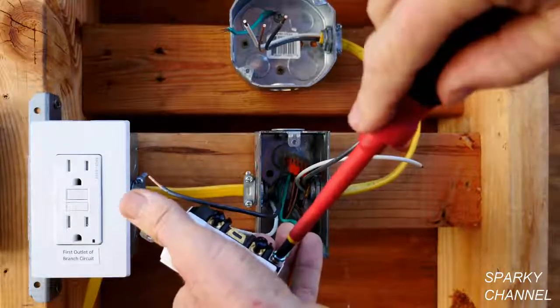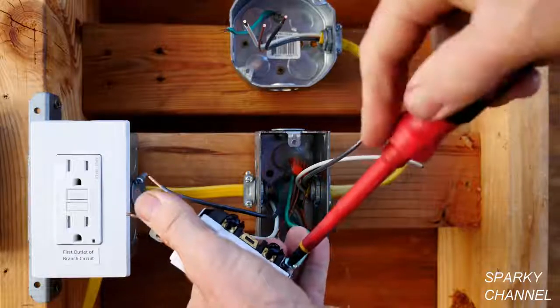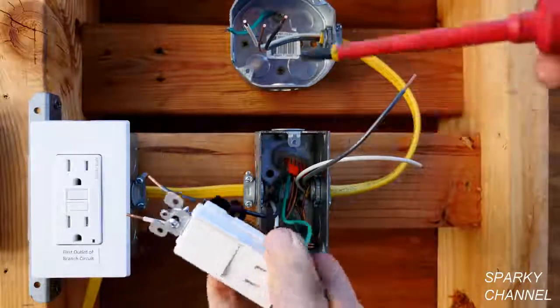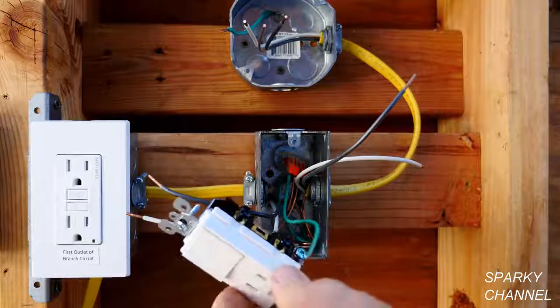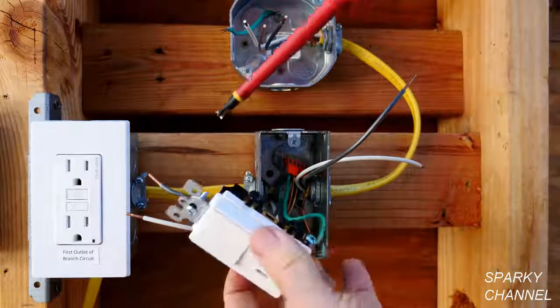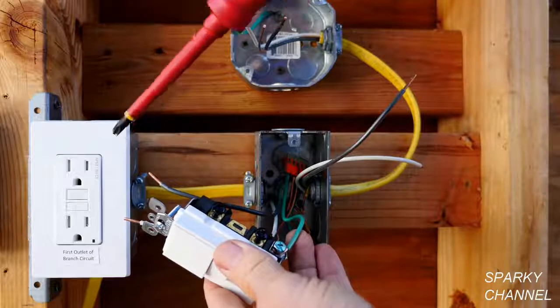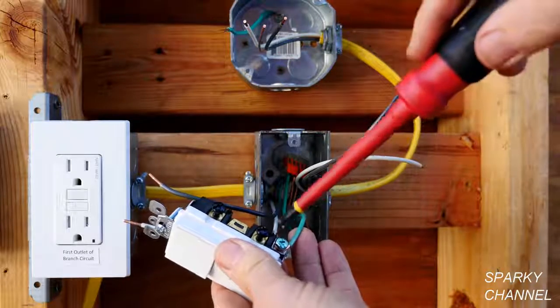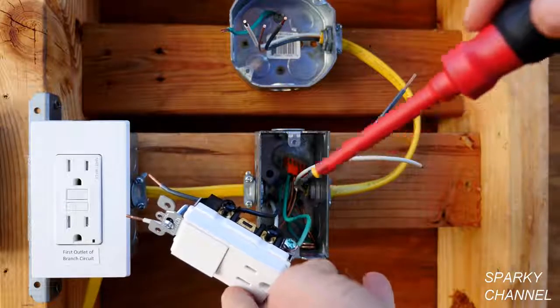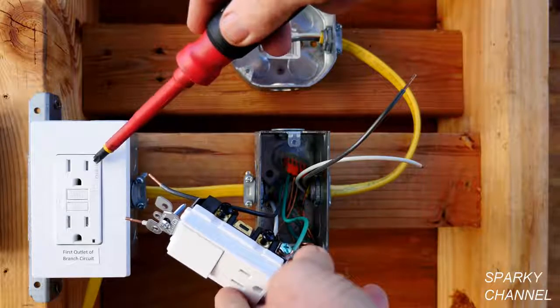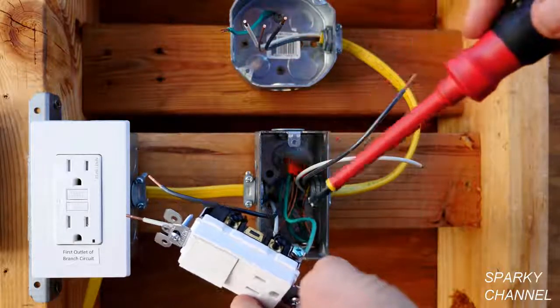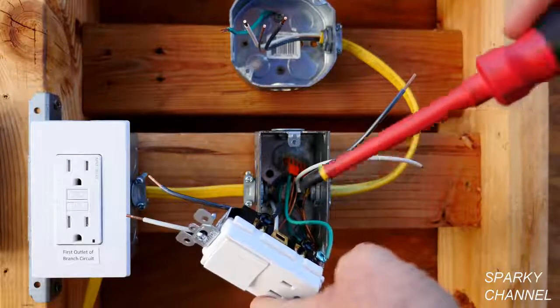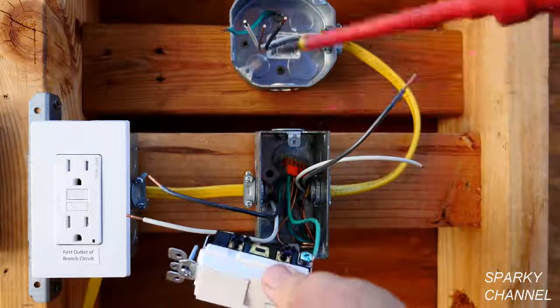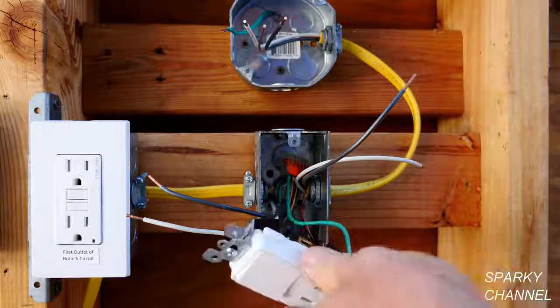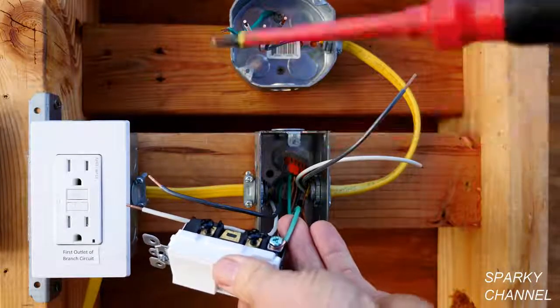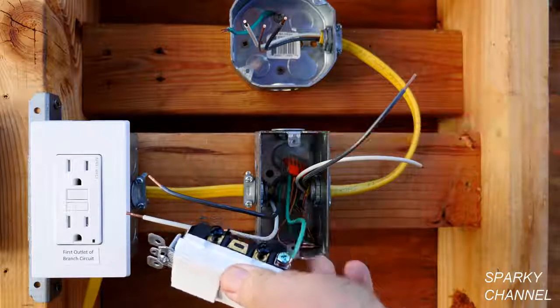Now let me make a point. Everything needs to be very, very secure. I mean, you always need to make very secure connections. But when your circuit has AFCI protection, it's extremely important that every connection be very secure, because this AFCI is looking for any kind of bad connection and it'll blow. Okay, so in order to prevent a lot of problems later on, make each connection very, very secure.